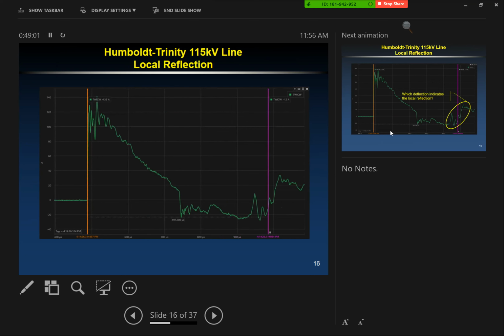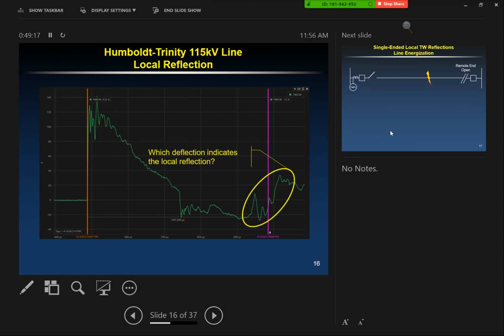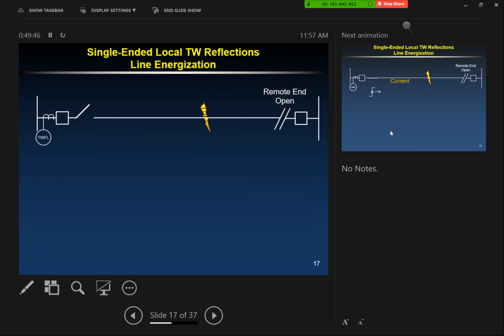There's also going to be a local reflection, as we saw in the Bewley lattice diagram. You'll first see the remote reflection, but local reflections happen too. Where does that occur? For this event, here's the point of interest, though you probably wouldn't spot it just blindly looking at the event. It's a muddy picture, not easy. You'll want to go after that first reflection point, which can be the remote end, like in this case, but even then it can be difficult, sometimes buried in noise. At that point you might pull up the Bewley lattice diagram and look at subsequent reflections, not just the first but later ones. So it's a little challenging.